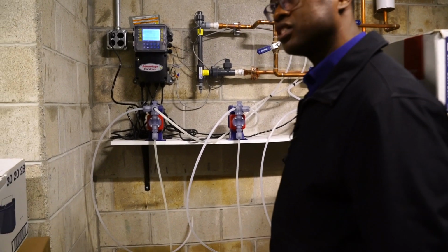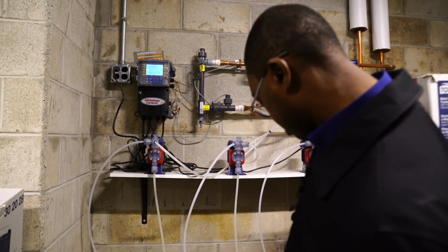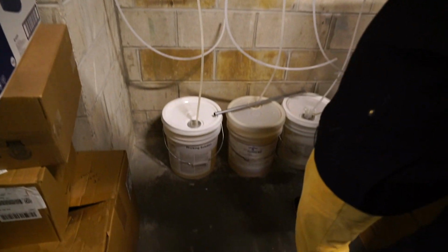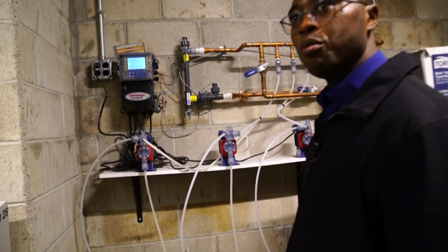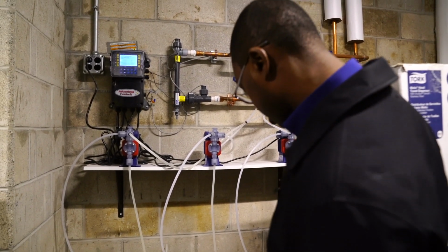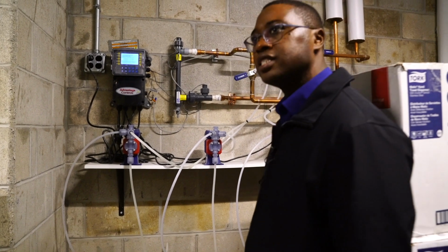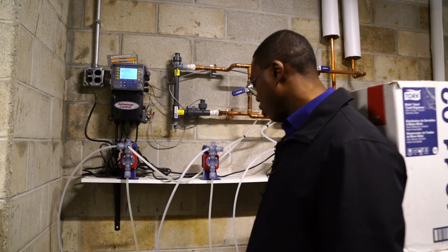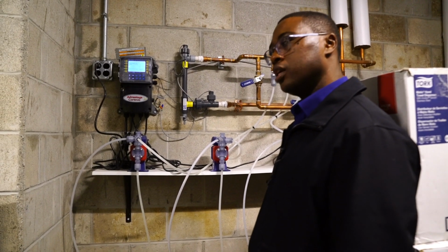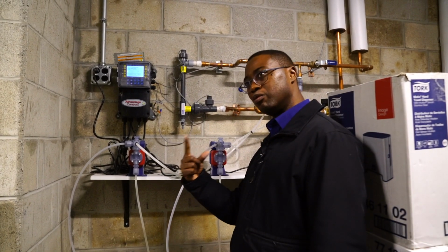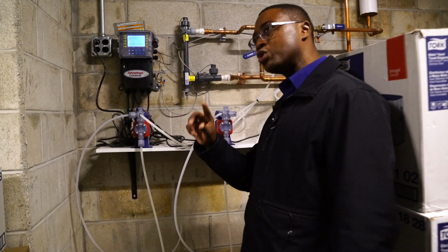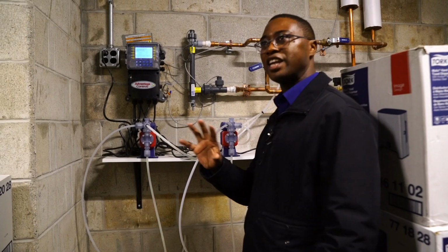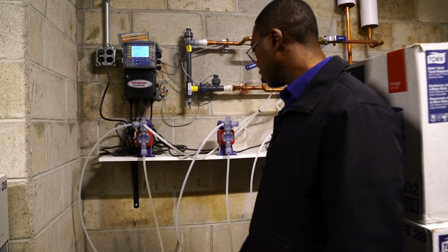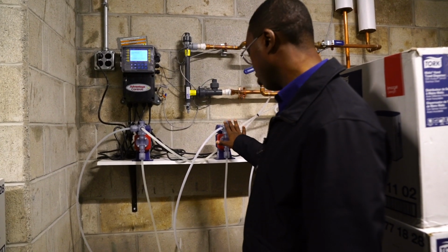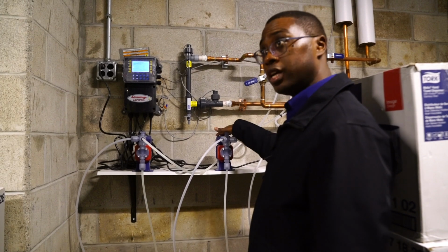The F900 chemical is the corrosion inhibitor and scale inhibitor. The Bromex is an oxidizer chemical, which is a bromine-chlorine based chemical. I think we call the other one the Beloside, which is a non-oxidizing chemical. So why do we have 2 biocides? Because sometimes bacteria get used to one treatment and then they start feeding off it. But if you switch treatments on them, you tend to kill them, you know what I mean? So it's good that you have this, and you also have your corrosion inhibitor and scale inhibitor for your cooling tower.